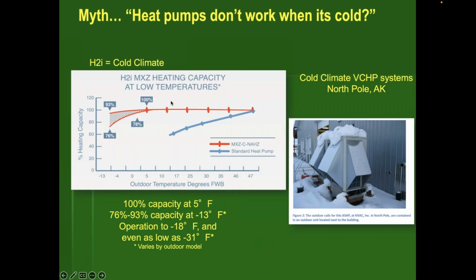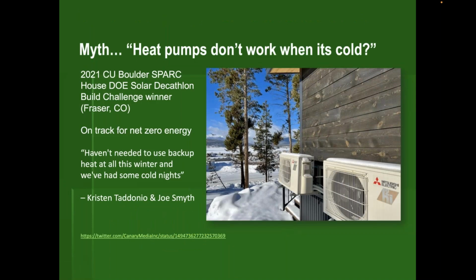Now, this is an important chart here. Check this out. This is a cold climate heat pump. And it is a myth that heat pumps don't work in cold climates. So here's an example of one manufacturer's. It can deliver 100% of capacity at 5 degrees, 76 to 93% capacity at -13, depending upon the equipment, and operation to -18, and even as low as -31. So that's the beauty of this equipment. They figured out some clever ways to take the waste heat off the compressor and recover it in order to make it work when it's really, really cold outside.